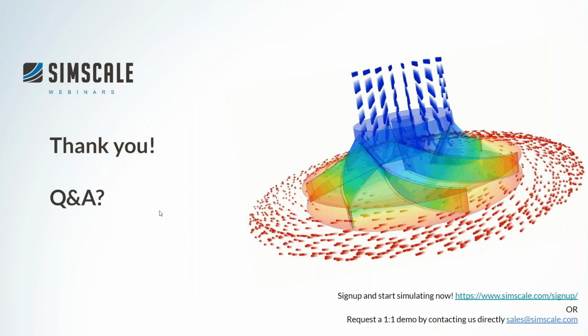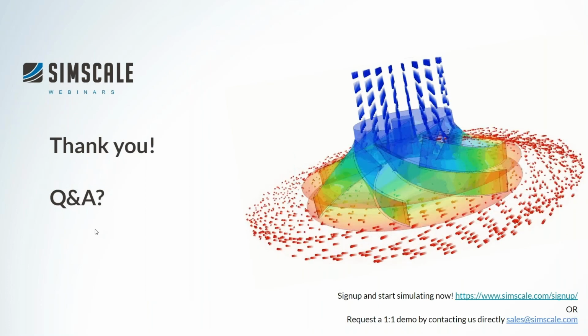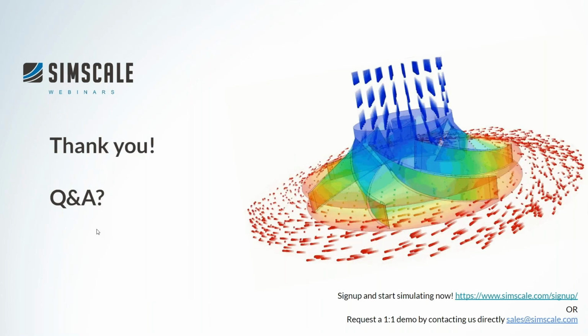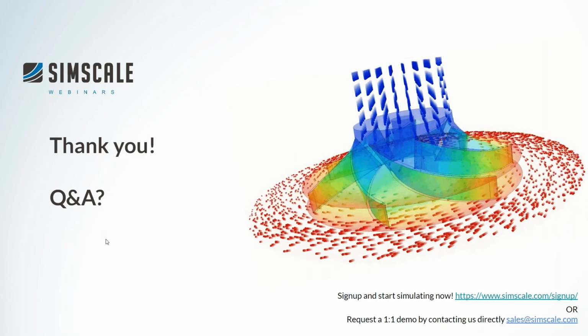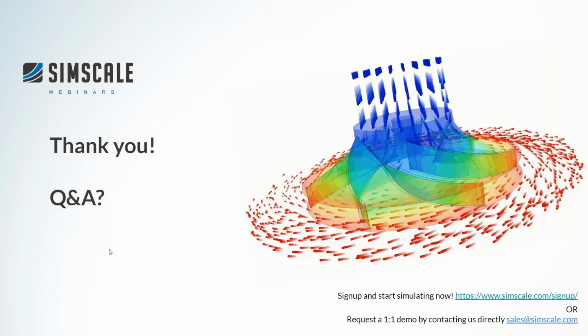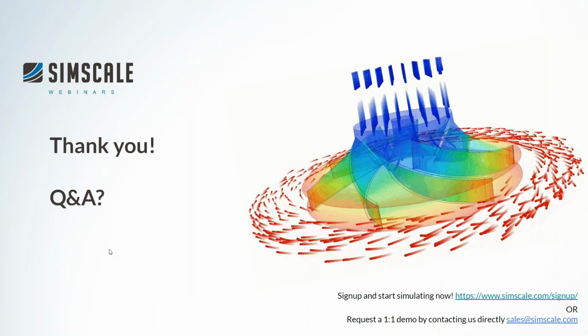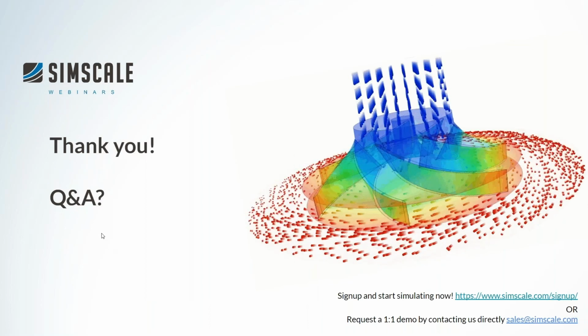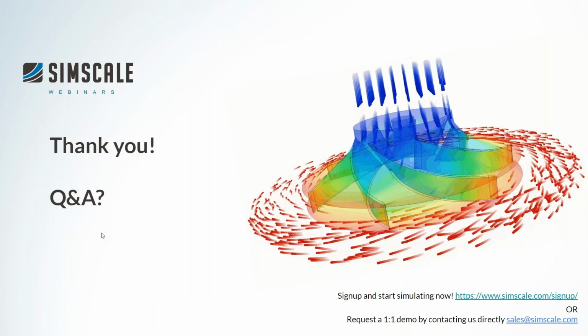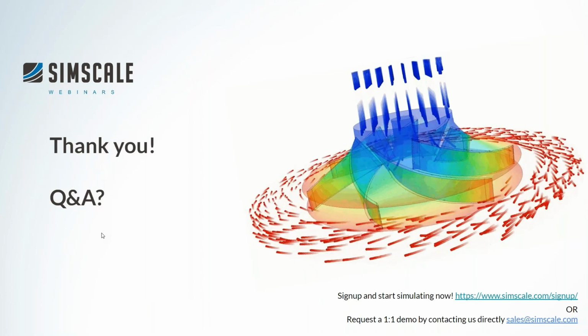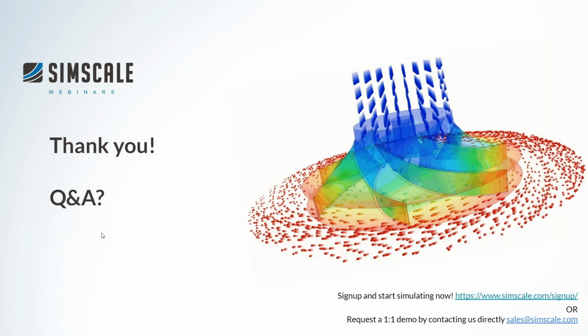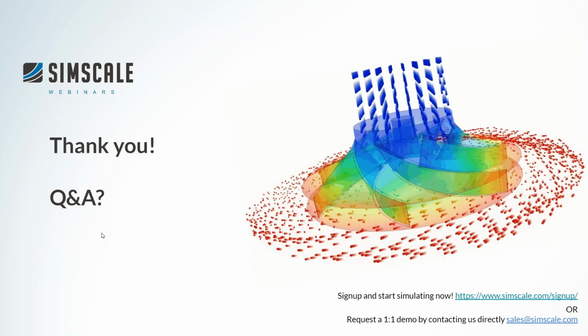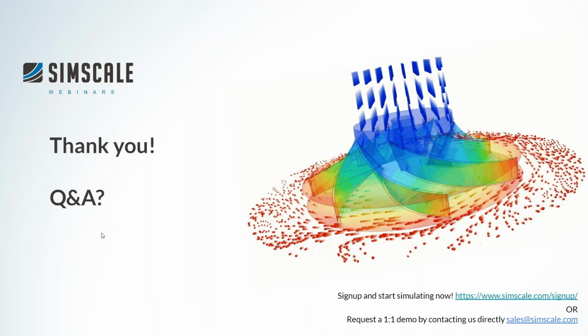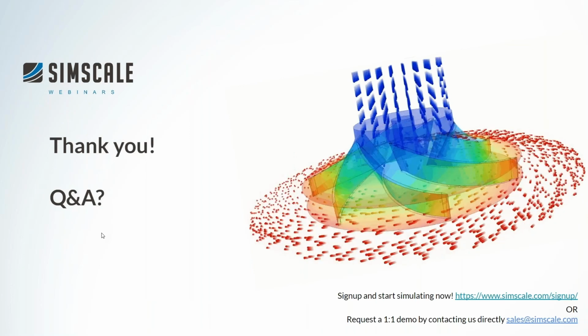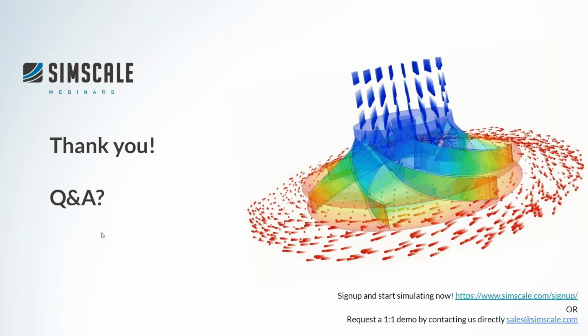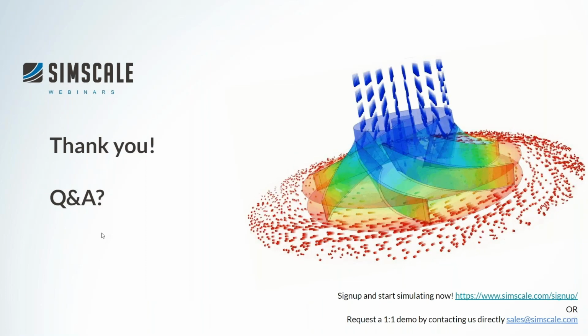Yeah, and it was, I think, a conscious decision. Tony also told us that we can neglect cavitation for this case. Maybe Tony, you have a few words to say about that. Normally cavitation is no issue for this kind of pump, so we neglect it. Of course, we have to recheck this with a newly designed impeller. Yeah, we have to recheck, but normally cavitation should be no issue.